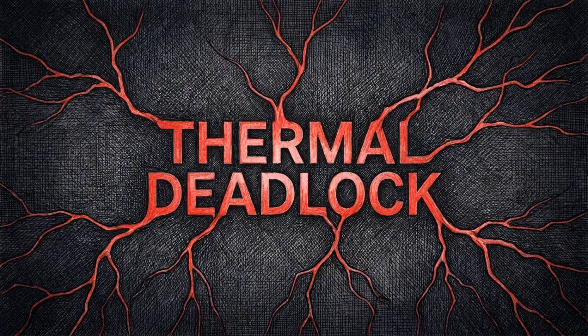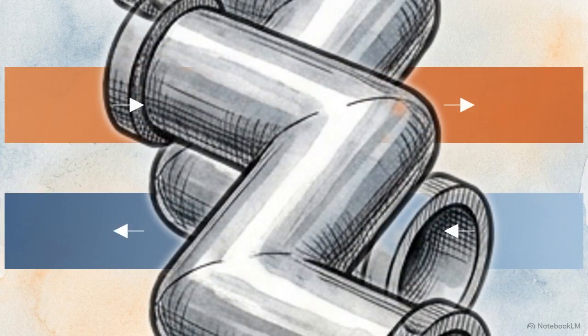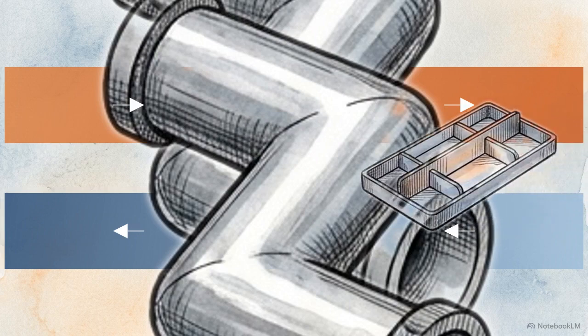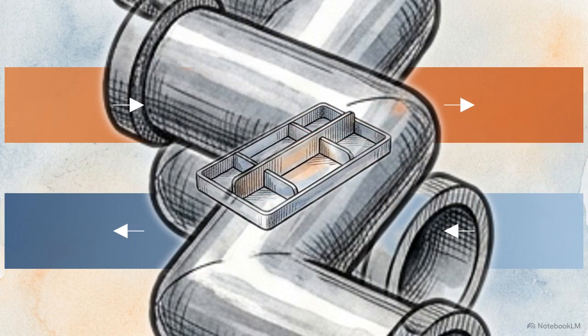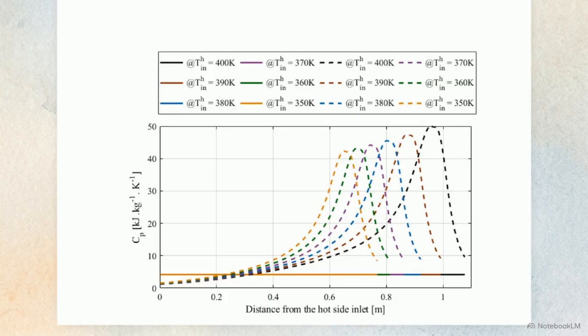We use this speed to hunt for the sCO₂ cycle's most destructive thermodynamic hazard, the internal pinch point. An internal pinch point is a specific location inside the heat exchanger where the temperature difference between the hot carbon dioxide and the cold cooling water drops to absolute zero. This graph charts the specific heat capacity. Because the CO₂ fluctuates so wildly near the critical point, the rate of heat extraction suddenly mismatches the cooling water's capacity to absorb it. When that happens, thermal transfer inside the pipe completely halts.